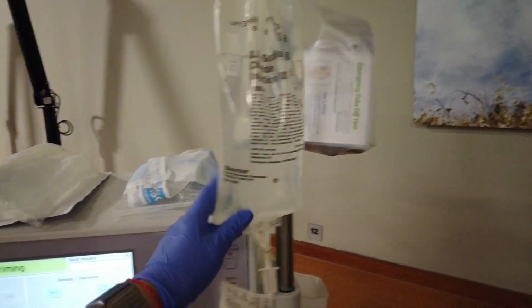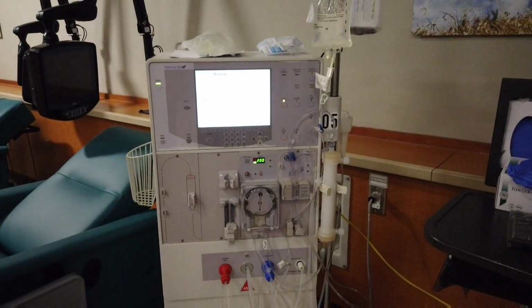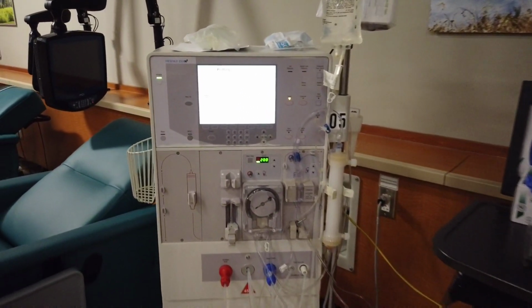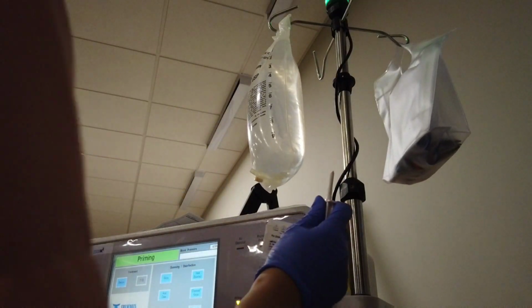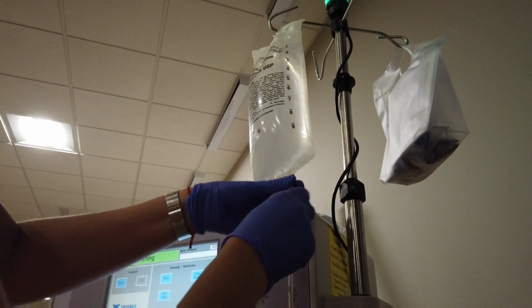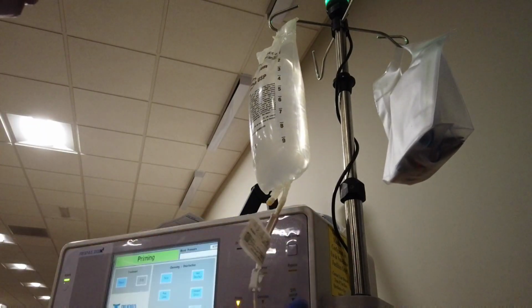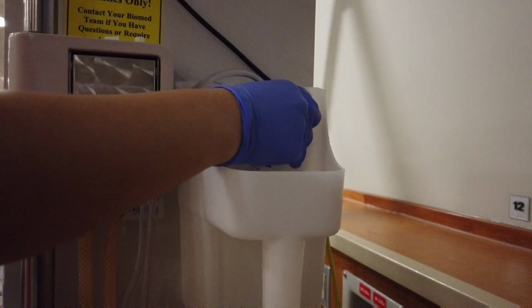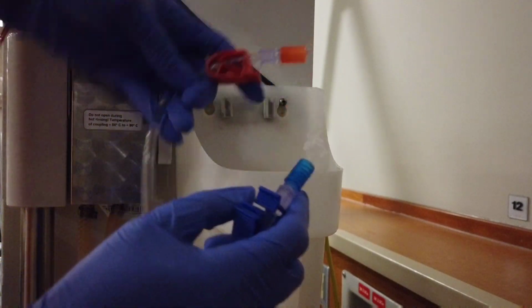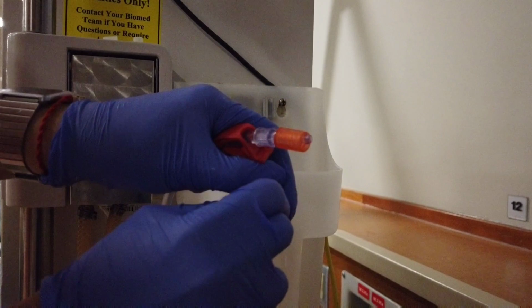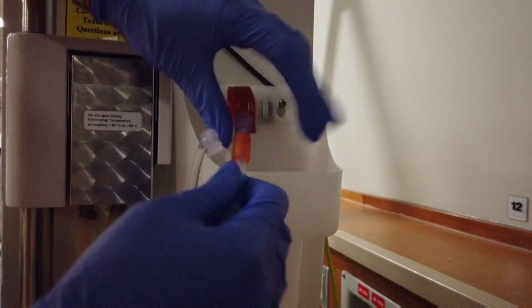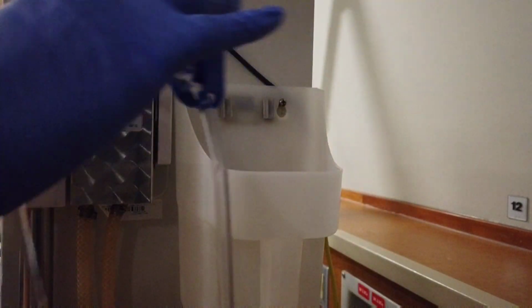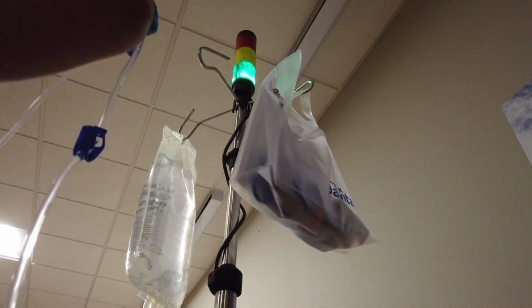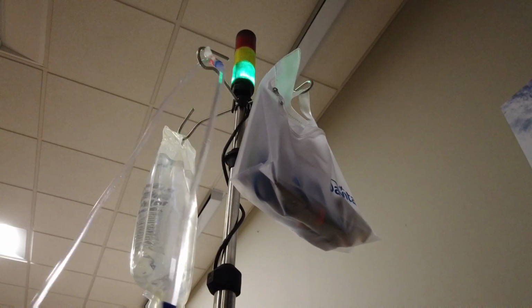But in this case, the type of dialyzer used needs a full bag, so here's the second bag ready once the first bag is consumed. Just keep on pressing prime if blood pump stops until bag consumed. Once empty, stop the blood pump and hook a new NSS bag. Now, connect the arterial and venous patient's end. After priming, the next step is testing, but before I can do that, the bicarbonate acid should be hooked first.